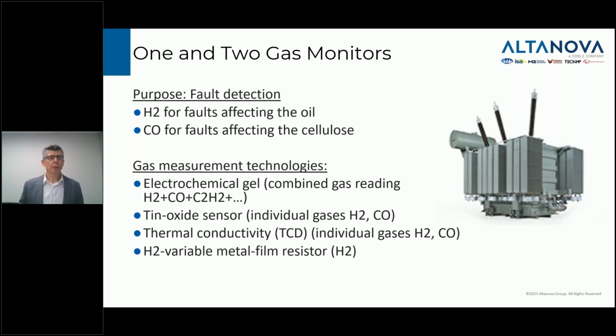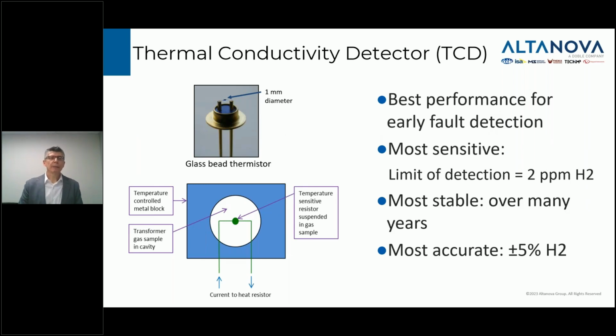And there are 4 different types of gas measurement technologies in the industry today in these kinds of fault detection monitors. I've made a list of them here for your reference. 3 of them require a gas extraction membrane. One of them, the last one, which is a hydrogen variable resistor, works directly in the oil. They each have some pros and cons. But the one I'm going to focus on today is the one that I think is best suited for the challenge of early fault detection. These monitors use thermal conductivity detectors to measure the hydrogen and also the carbon monoxide in some cases. I think they're the best for early fault detection because they're the most sensitive. They're actually an order of magnitude more sensitive than other solutions.